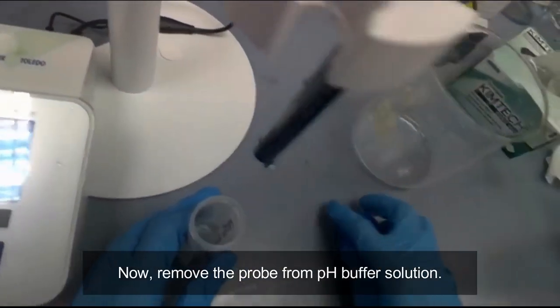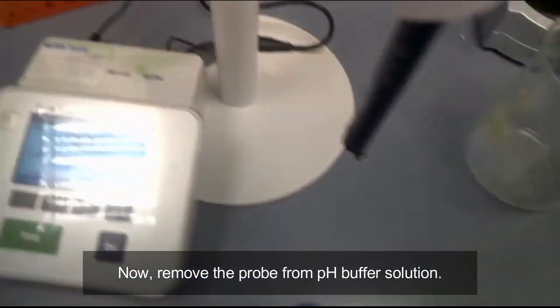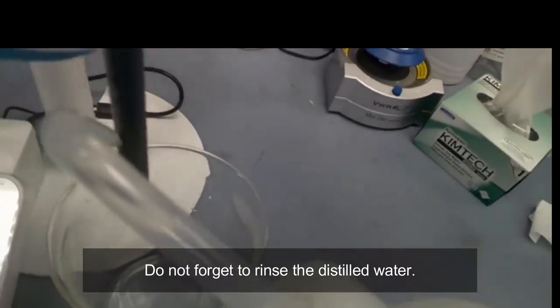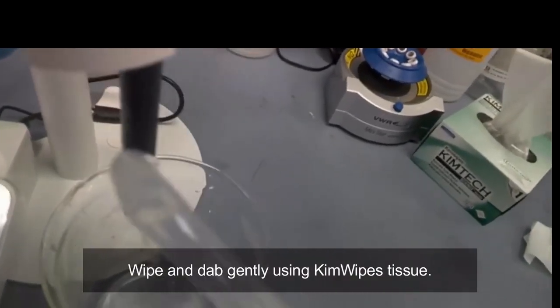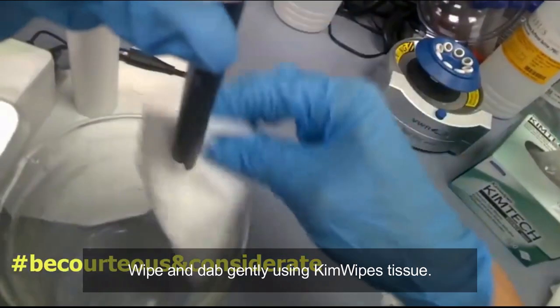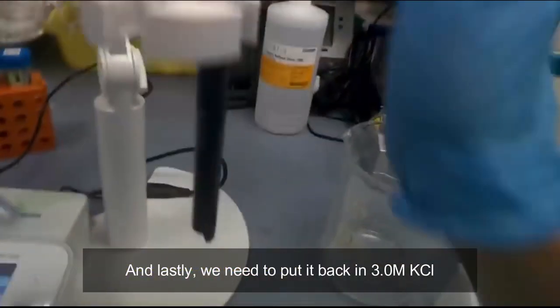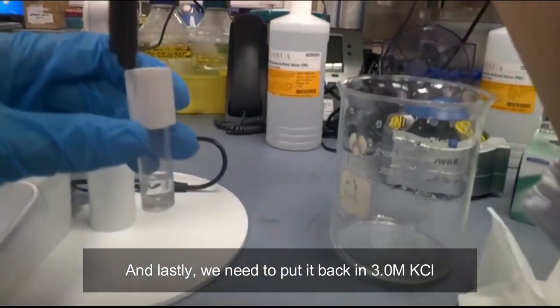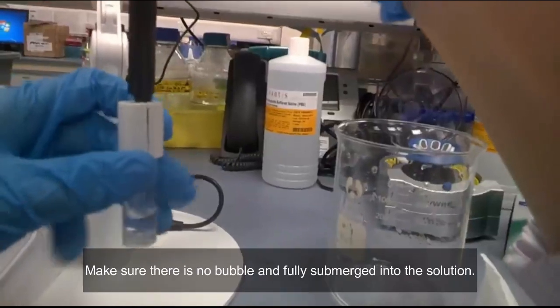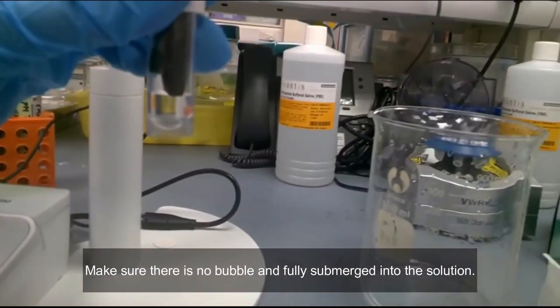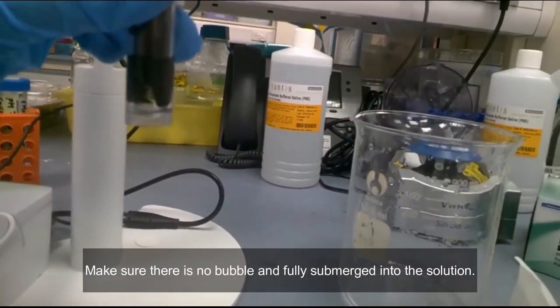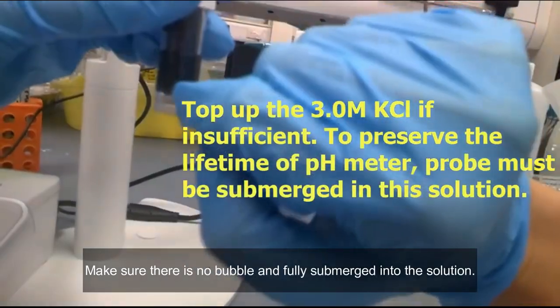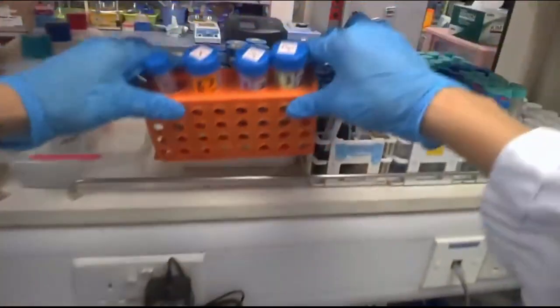Now remove the probe from the pH buffer solution. Put it back on the stand. Do not forget to rinse with distilled water. Wipe and dab gently using Kim wipes tissue. And lastly, we need to put it back in 3.0 M KCl to preserve it. Make sure there is no bubble and it is fully submerged in the solution. Put back the buffer.